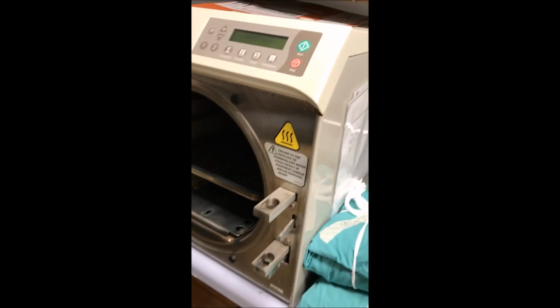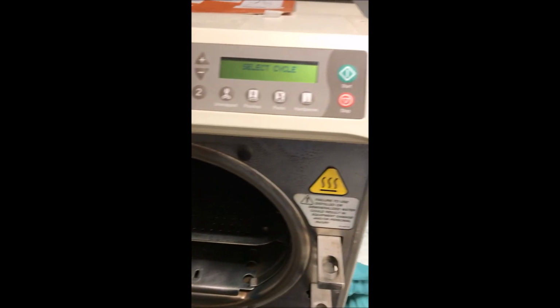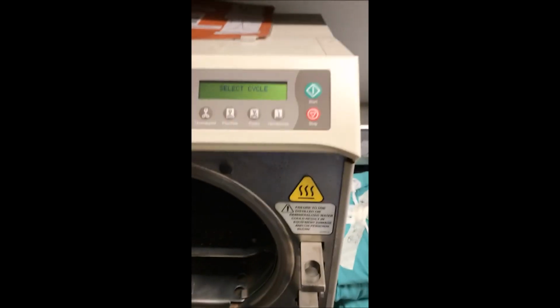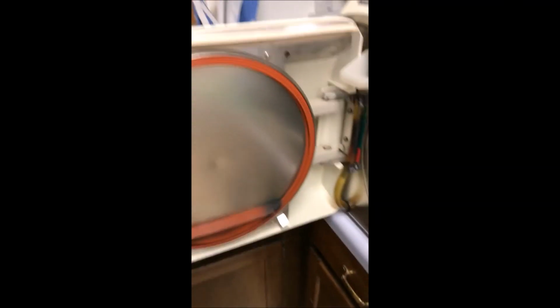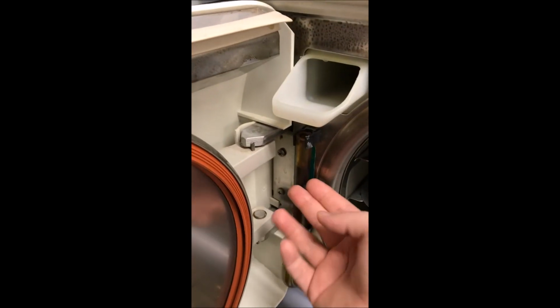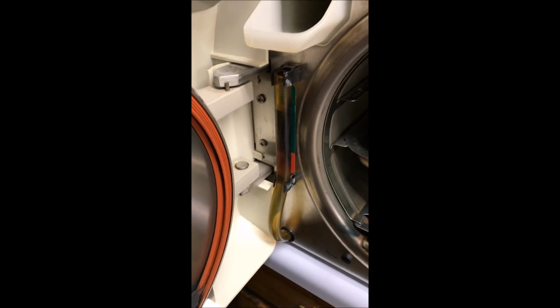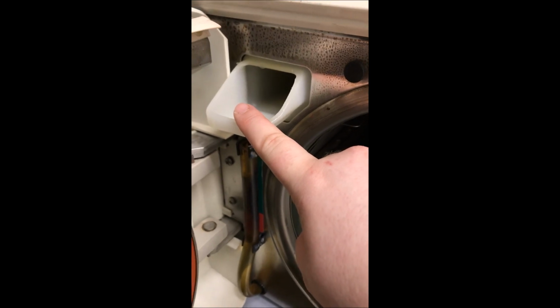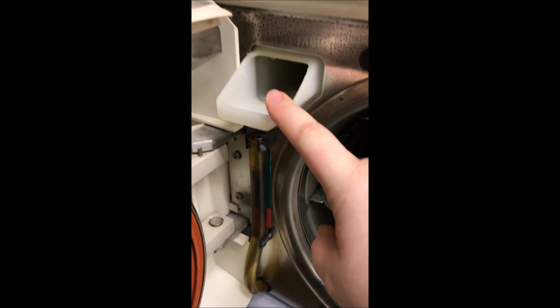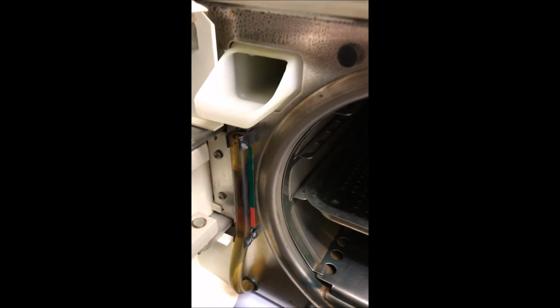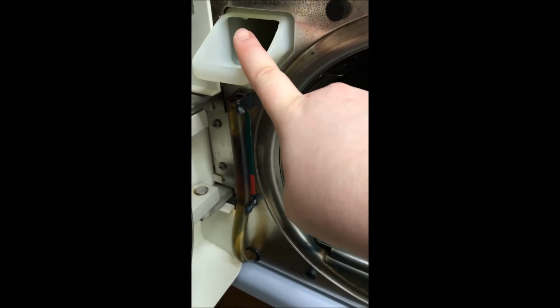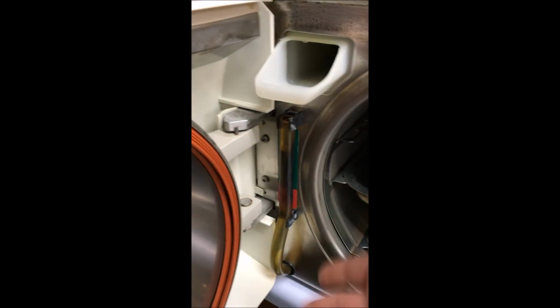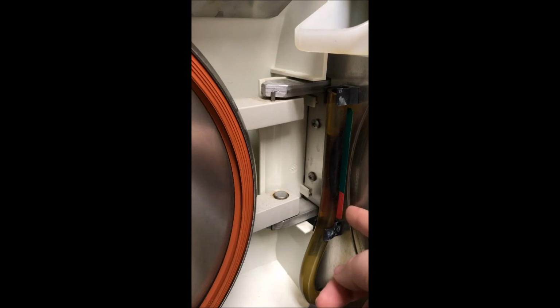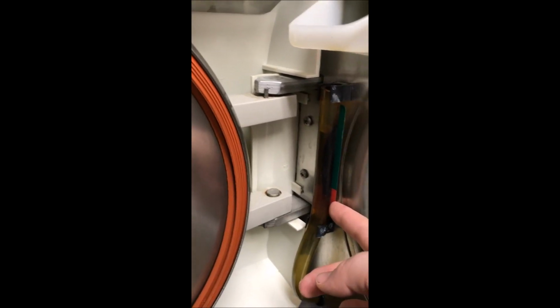This is our autoclave. It already has pre-programmed cycles for us. We do make some adjustments to it with the speed of how long it takes to dry the instruments themselves. We do bi-weekly maintenance on this machine. This is a drain tube, so we actually pull this tube down and then allow it to fill a bucket, and then we will fill this valve with a mixture of distilled water and diluted product called Speed Clean. We run that through an entire cycle, and then we drain it again, and then we wipe out the inside of the autoclave and everything, and then we refill this with distilled water so that we can autoclave again. It has a gauge here to let us know whether or not we need to add water. If it's red, we need to add more.